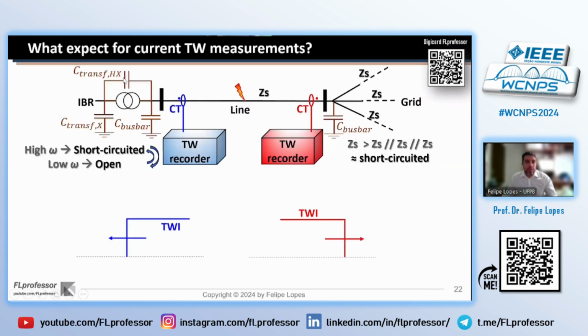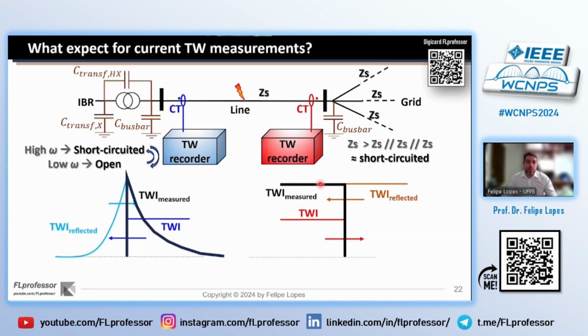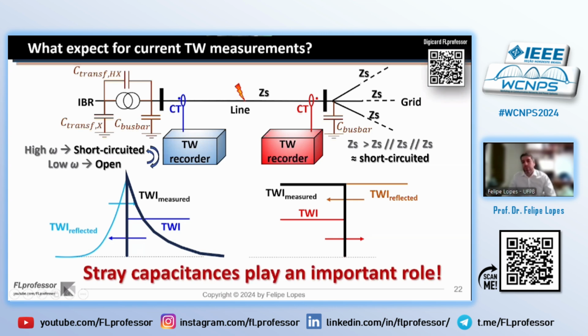So it shows us that there are stray capacitances over the transformer and the busbar capacitance, and they will affect the measurement, because when we consider these capacitances, at least from the perspective of transients or surges, they are in parallel with this transformer. So these capacitances will dictate the behavior of the measurements. And actually what we will see is something like that, with reflections. And at the end of the story, we will measure a step change on the grid side and a quick step here, which decays exponentially after some time. So the stray capacitances play an important role for traveling wave-based applications, and this is a topic that we have investigated a lot in the past years.